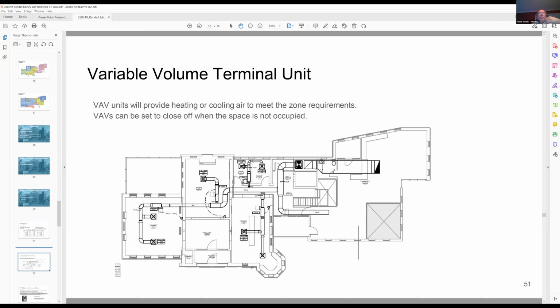So when I mentioned variable flow or variable air volume into the space, we look at how we can break the spaces down into different zone controls. A variable air volume unit is a device that will regulate the amount of air coming into the space that is needed just to heat or cool it. There's no excess air. It's not a constant volume system. You bring the right amount of air in to condition it. Again, that helps us keep the total amount of airflow down to a minimum and not waste energy. It also allows for better temperature control within the different zones.